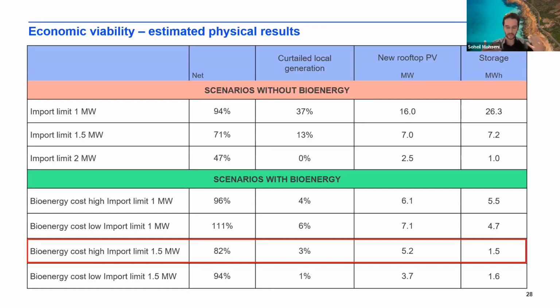But you can see the curtailment is really low. It's only 3%. That's very small, and part of that is because we only have a small amount of added PV. So it's an extra 5 megawatts, and also we only have a small amount of new battery, only 1.5 megawatt hours. So of course you'll get a very low battery autonomy in comparison to other scenarios. It's just less than 1 hour, but that can be okay, especially for short-term outages, and like Heather mentioned earlier, if you turn off the big loads, it will get much higher. You can sustain the loads for an extended time.